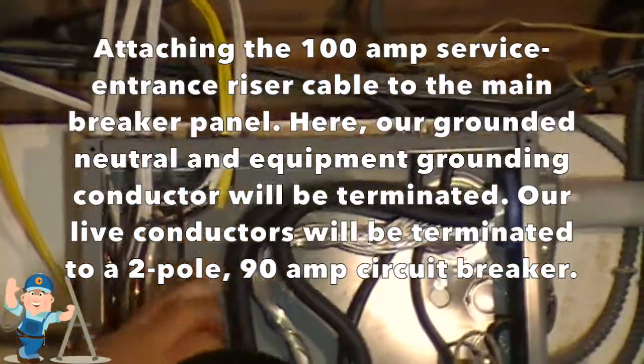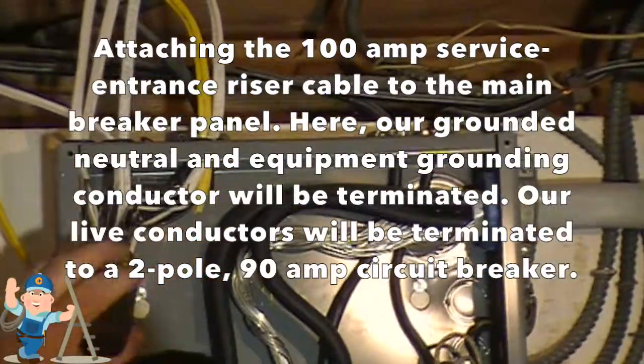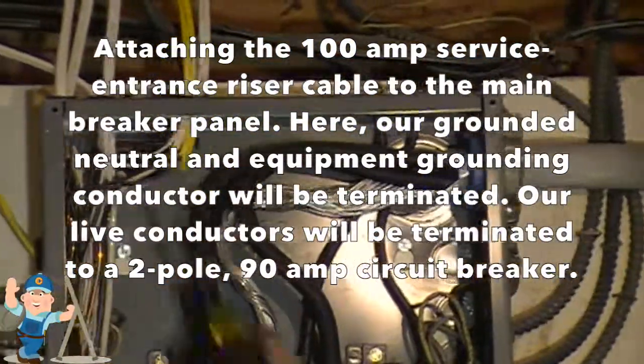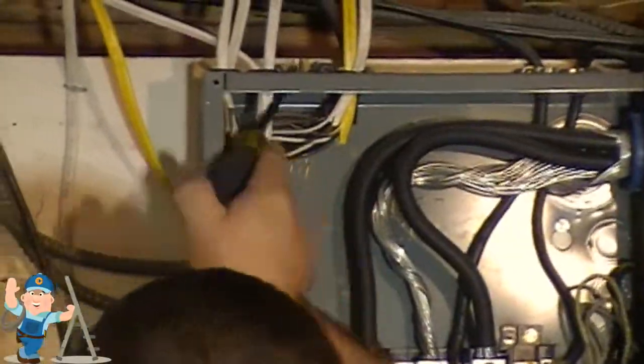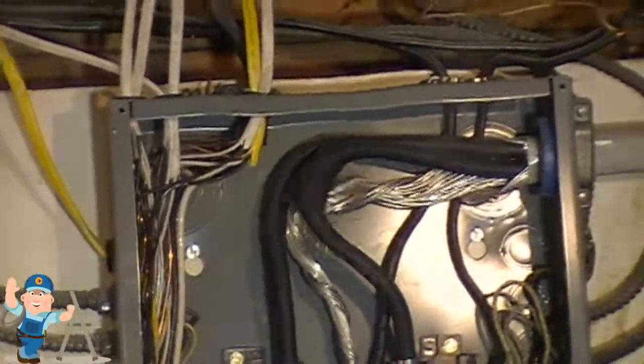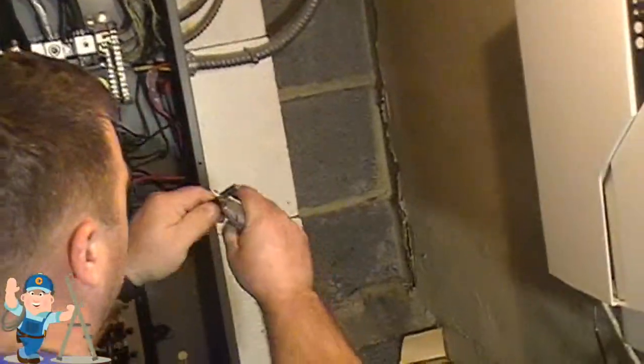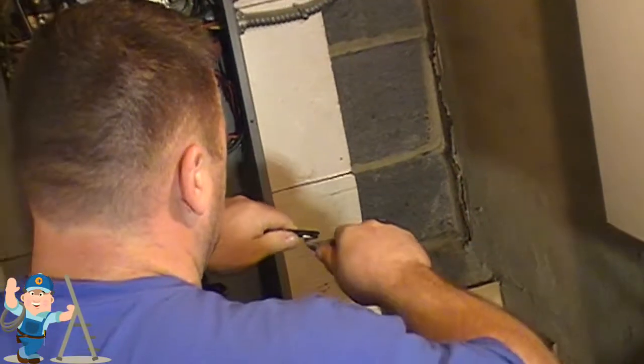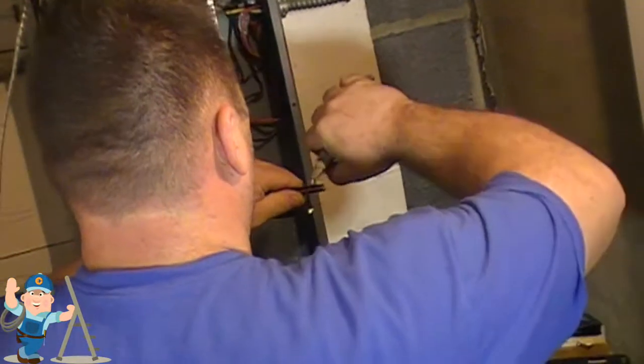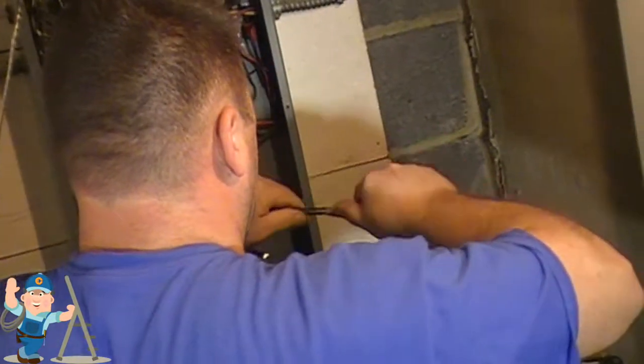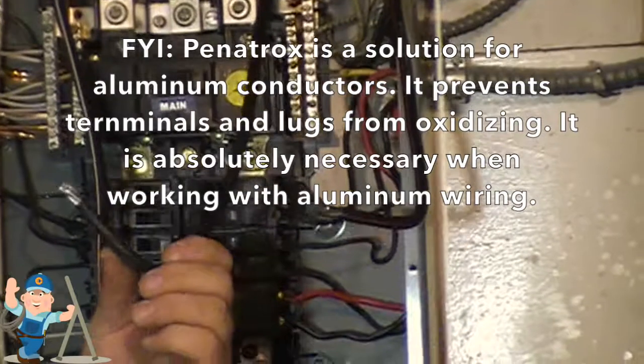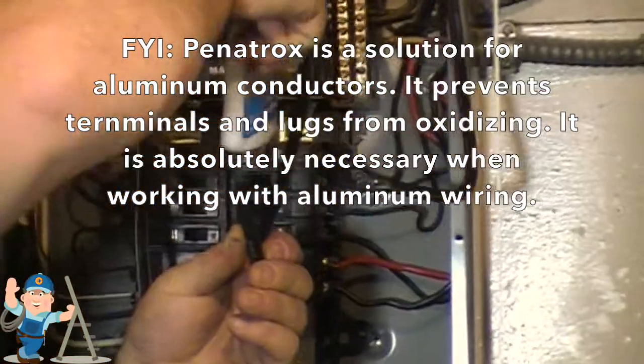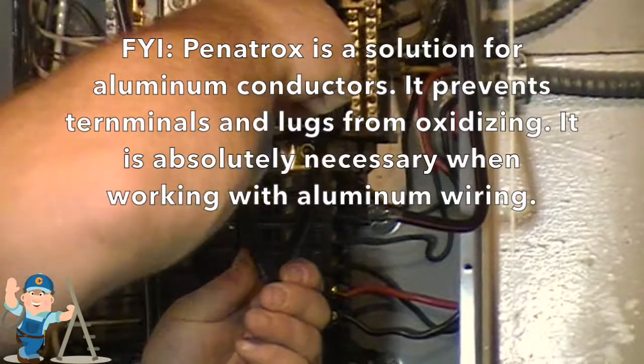So here we are, installing the service entrance riser cable into the main breaker panel. You can see me there working. I'm trying to get the knockout out of the top of the panel enclosure there so I can put in a 1-inch connector where I'm going to be putting in the service entrance riser cable. Now, the service entrance riser cable is a 4-wire assembly. It's got two number 2 American wire gauge aluminum conductors. I'm sorry, 3. So you'd have 2 hots and a neutral, and of course the ground is a little bit smaller than the ungrounded conductors because that's what the National Electrical Code calls for. So that's how it comes.